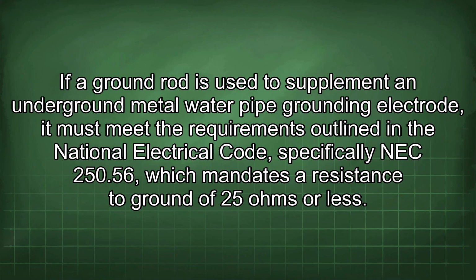If a ground rod is used to supplement an underground metal water pipe grounding electrode, it must meet the requirements outlined in the National Electrical Code, specifically NEC 250.56, which mandates a resistance to ground of 25 ohms or less.